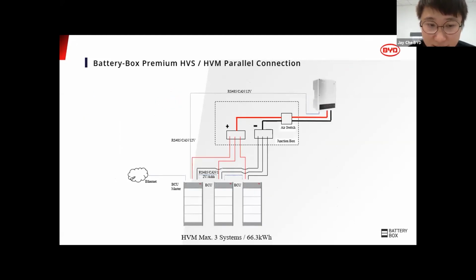This is one parallel connection example with the GoodWe series, 3-phase hybrid. You can see it's very simple - there's no additional equipment needed, like with other battery manufacturers who need a combiner box or residual protection. With BYD, all you need is the communication cables, the power cables, and a bus bar that connects the positive and negative. You have an air switch or circuit breaker so you can turn the whole system on and off. In some countries this is required, in others it's optional. For each battery, we have a built-in circuit breaker so you can turn the battery off and on individually, with no additional hardware required.